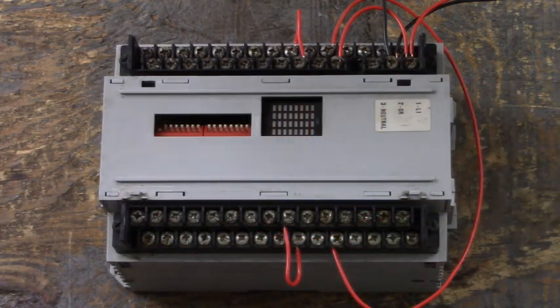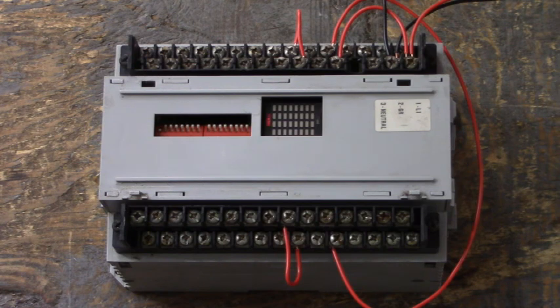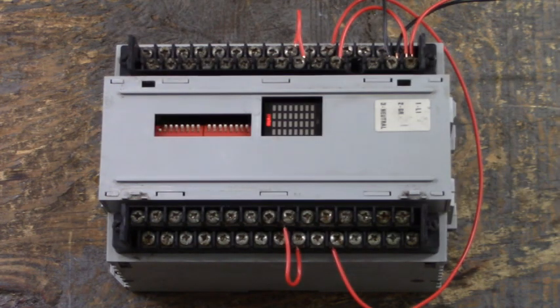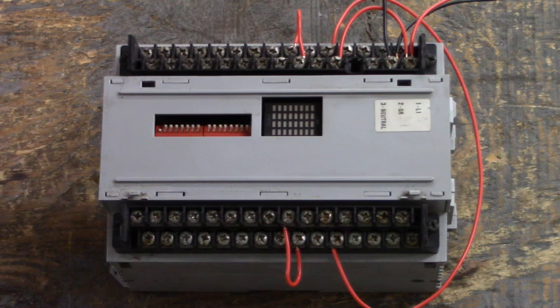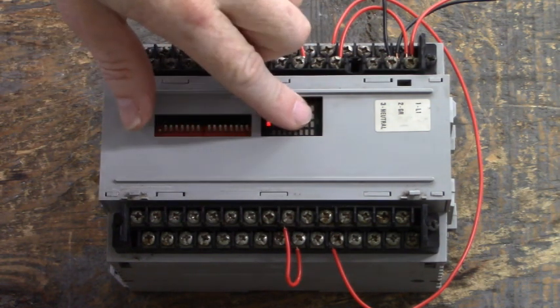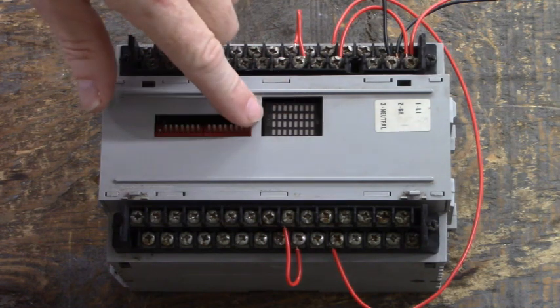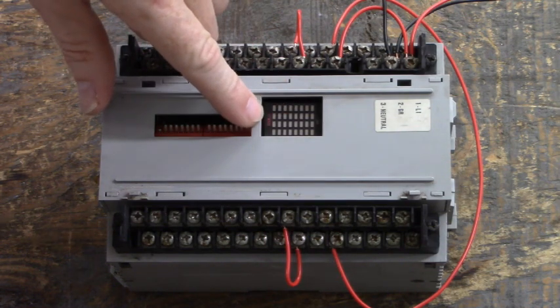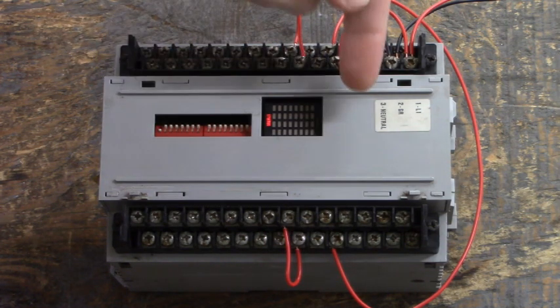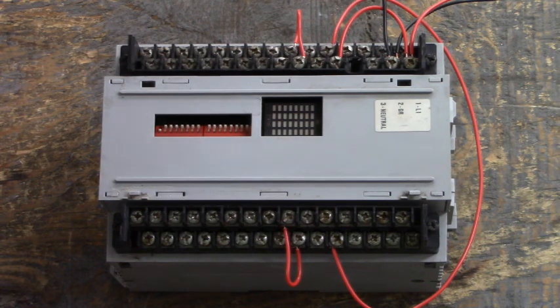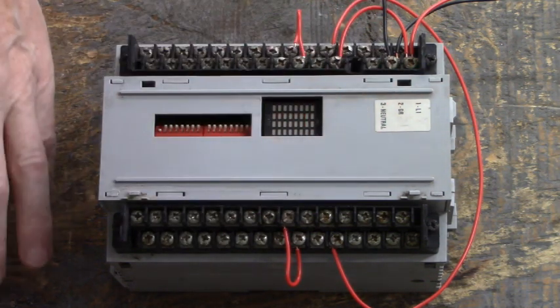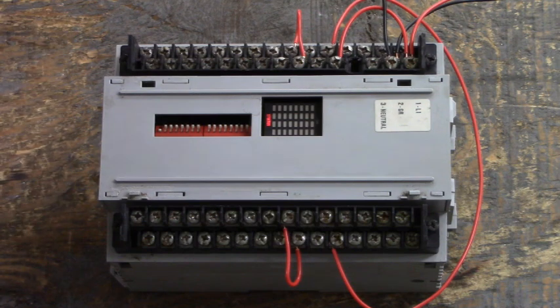Alright, let's power up the input module. We've just applied 120 volts AC to L1 and L2, and you can see that the COM LED is off and the status LED is blinking. That indicates there's no communications into this input module - that's an alarm. Let's go ahead and test the inputs.